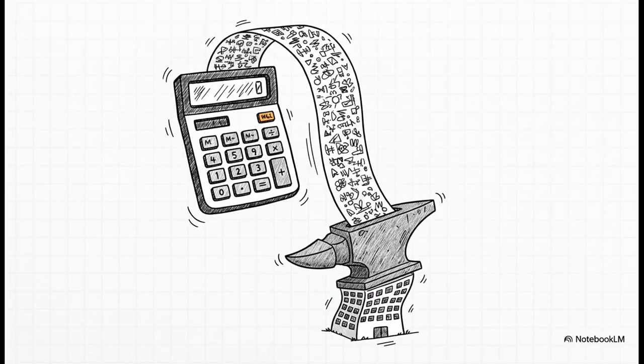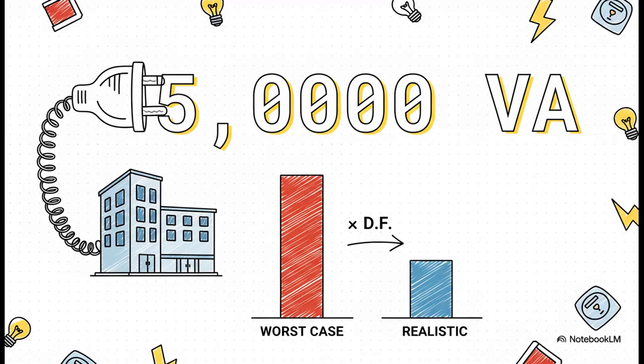So if you actually calculated the load based on that worst case fantasy, you would end up with a truly massive number. For a pretty normal sized office, you're looking at a potential load of something like 50,000 voltamperes. That's the unit we use to measure the total electrical load.